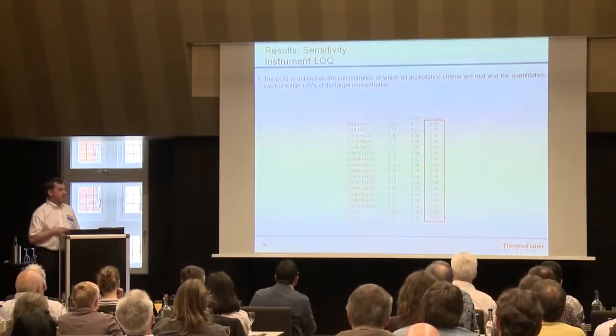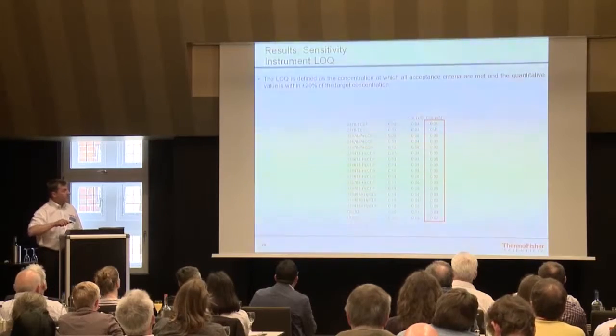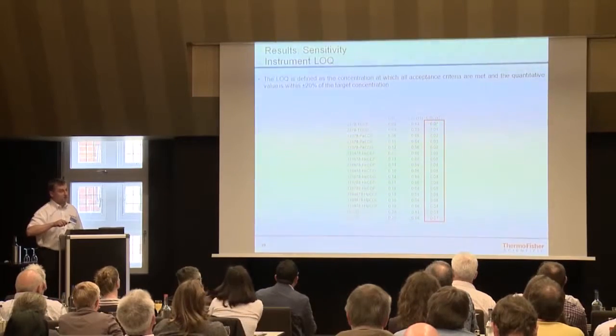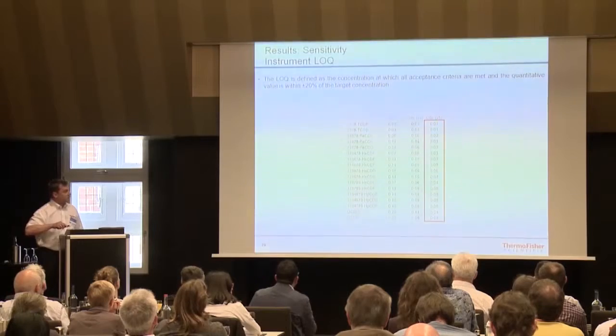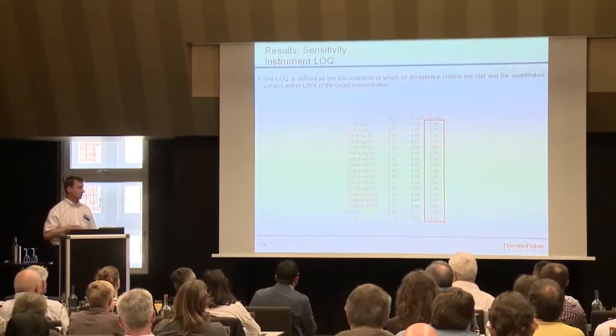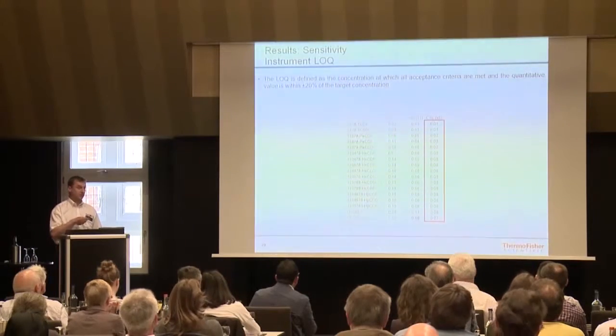What we did was take a CS1 standard and dilute it a few times across different concentration ranges, inject it a few times, and look at the criteria — ion ratios within 15%, response factors within 20%. This shows the LOQs calculated for each of the native compounds in five-times-diluted CS1. There's an incremental trend visible, which is due to the fact that the CS1 standard contains higher amounts of octa-chlorinated compounds.